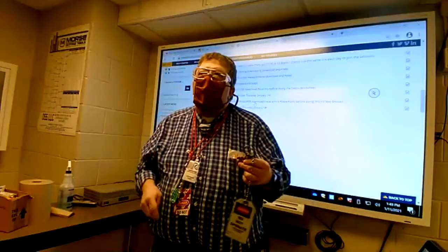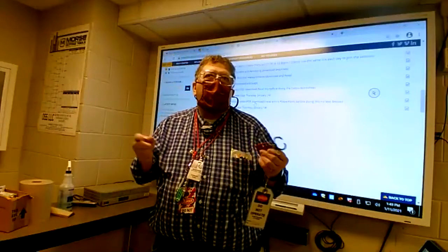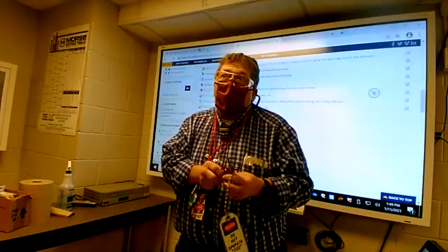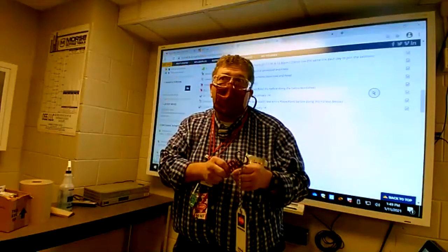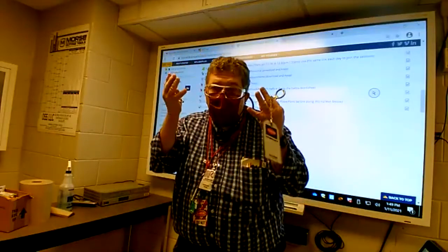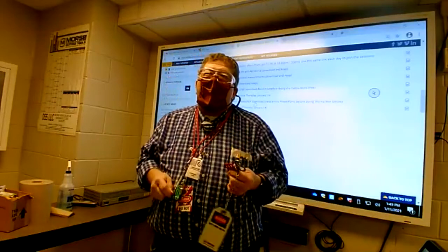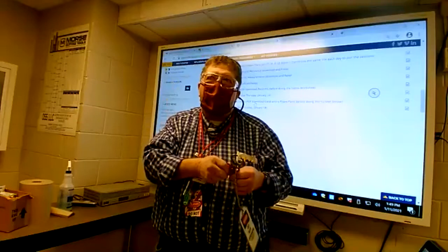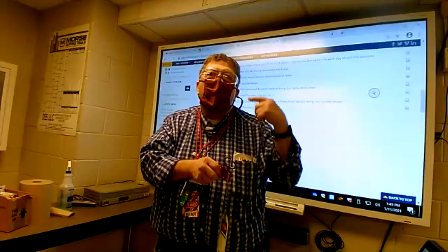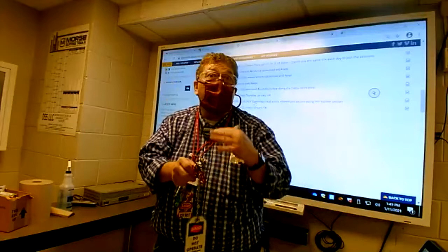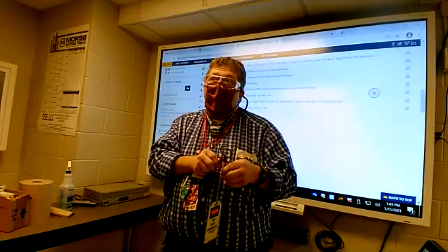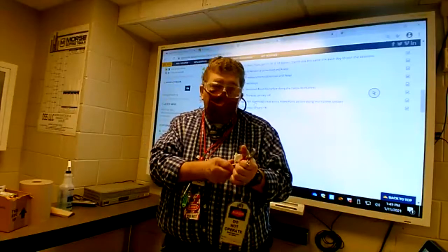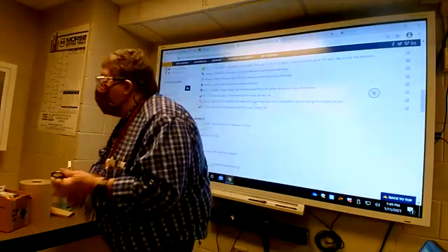And then you get on down to the end of it, you're going to let everybody associated with this machine know you're getting ready to unlock it and power it back up. So all of those steps are involved in there. It's not a matter of it just being you that knows what's going on. Your machine operator needs to know it. Your supervisor needs to know it. Production planner, whoever, they all need to be in the know before you do it, when you're working on it, and when you're done and getting ready to release it. Everybody needs to be in the know about that stuff, to keep in policy, keep safe, and keep everybody in the know about what's going on.